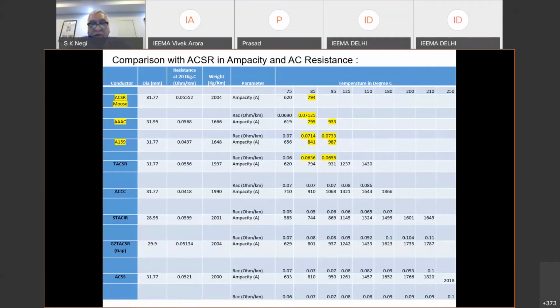Or the utility should think of designing a tower and type testing it with AL59. I find very few. I don't find any. I would like to be enlightened in the panel discussion whether any tower has been type tested with the AL59 conductor. So at that point of time, it is the designer who comes into the picture, and the conductor manufacturer, sag tension calculation, conductor designer come into the picture. They advise how AL59 in the existing tower can be used.